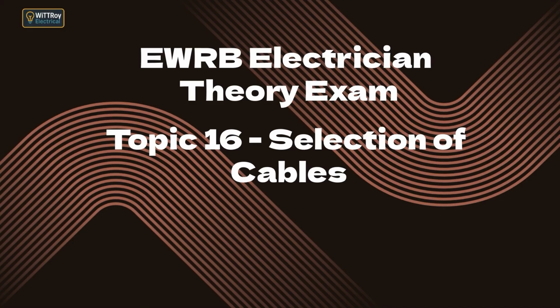It must also withstand the short circuit energy, meaning it survives the fault current long enough for the protective device to disconnect. Finally, the cable must meet the requirements for voltage drop and earth fault loop impedance, ensuring that supplied equipment operates correctly and protective devices trip within the required time. Only when all of these conditions are satisfied can a cable be accepted for use as a main or sub-main.